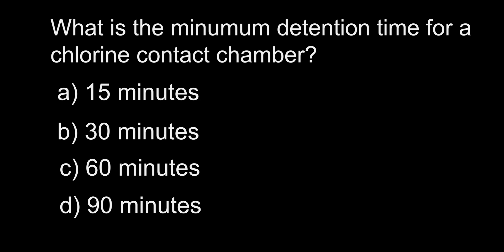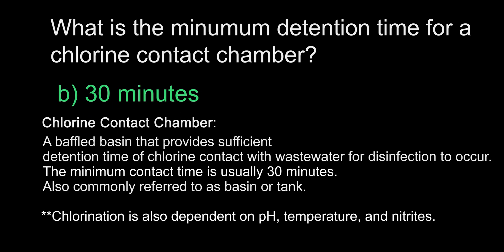What is the minimum detention time for a chlorine contact chamber? A. 15 minutes, B. 30 minutes, C. 60 minutes, D. 90 minutes. The answer is B, 30 minutes. This is a rule of thumb, and the definition on screen is directly taken from the Sacramento State College textbook, Operation of Wastewater Treatment Plants. However, what is taught in textbooks doesn't always apply to every situation or treatment plant. It's important to understand that chlorine contact time is influenced by factors such as pH, temperature, and nitrites.